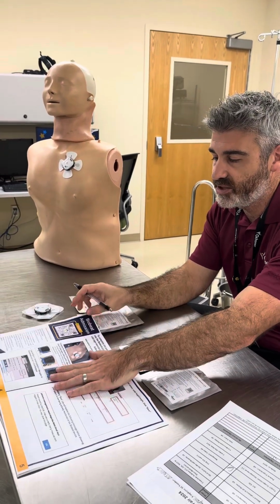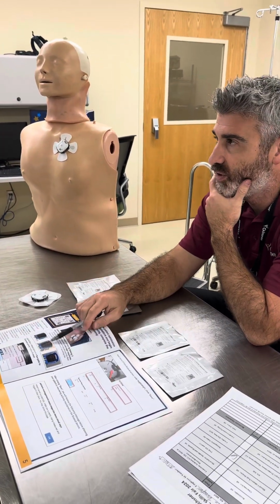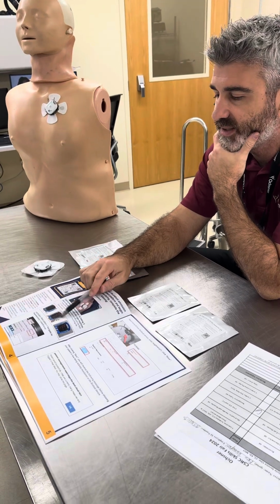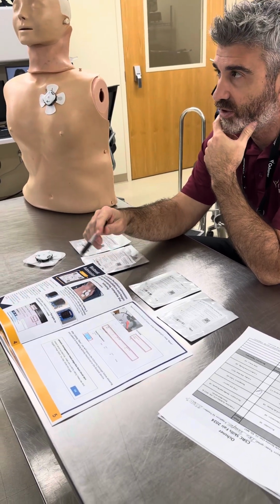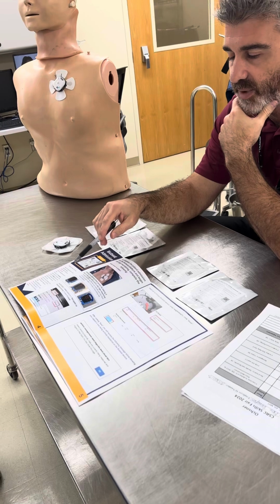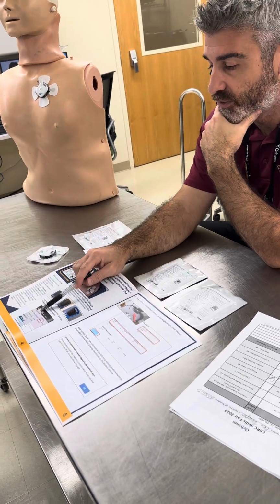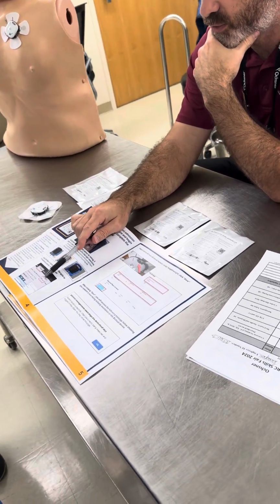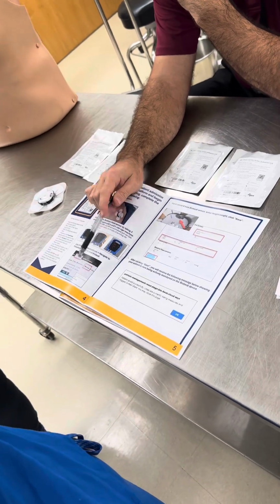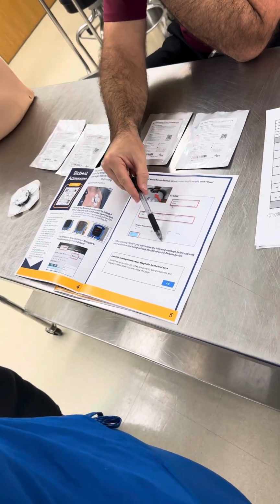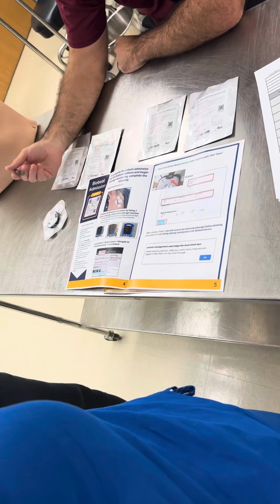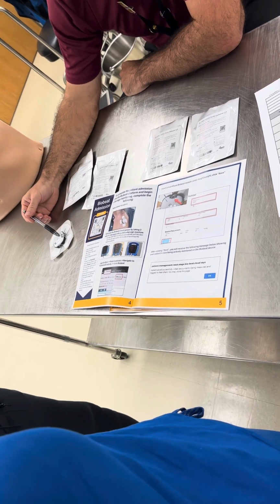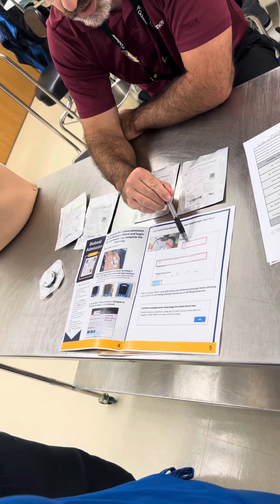When you're admitting a patient into Biobeat, we do have to do the 3 sets of calibration vitals at the bedside. That may change soon. We might reduce that down to 1. That's kind of TBD. You go into your flow sheets. If it's available on your floor, there's going to be this little Biobeat launch button. You click that. It opens up the Biobeat platform here. The only things we're having to input now are a little serial number off the device. We're putting that in here.